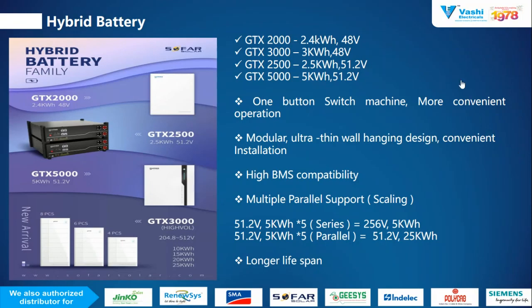Now, if these 5 batteries are connected in parallel mode, then you get 51.2 volt and your kilowatt hour increases, meaning 25 kilowatt hour. So these are the different parameters that you can consider for the hybrid inverter also. You can easily connect this kind of battery in series or parallel as per your requirement of backup time. So this is all about the hybrid inverter batteries.